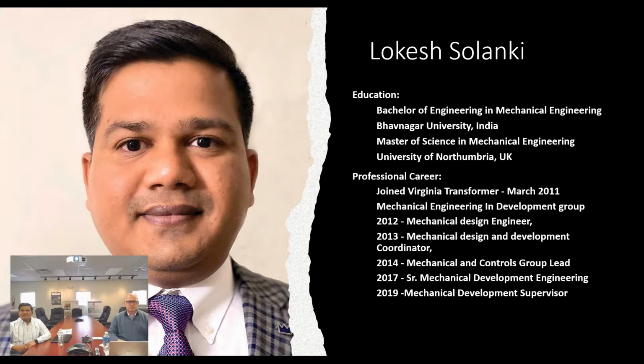Okay. This is somewhat similar to the question that we had yesterday, whether there would be any effect on the sound by changing the oil. The basic theory of sound transfer has the density of the surrounding as a factor. So if you have higher density, you can reduce the transformer noise transfer. However, when the transformer is in operating condition, mainly at the max level or the max FA rating of the transformer, the heat factor or the temperature factor comes into the picture.